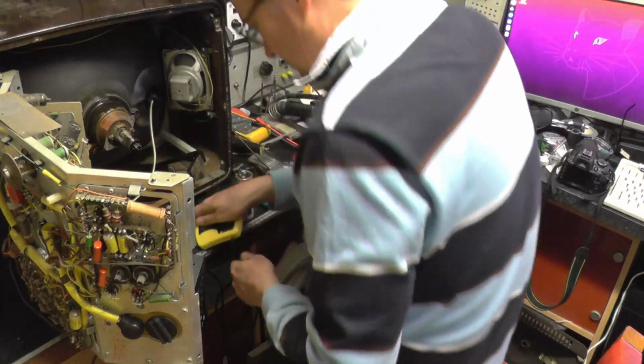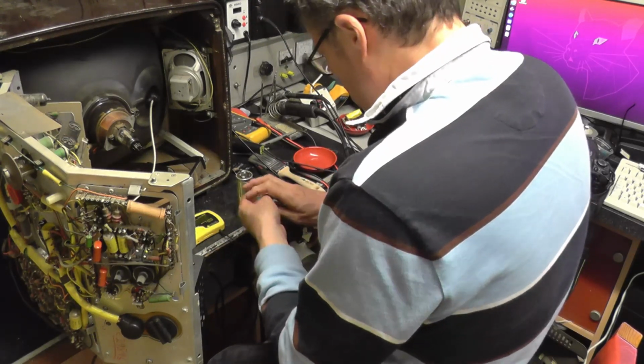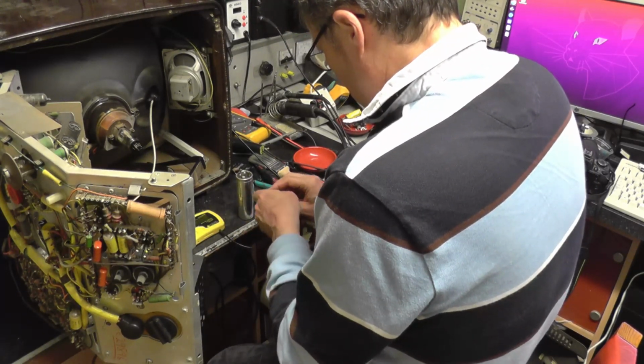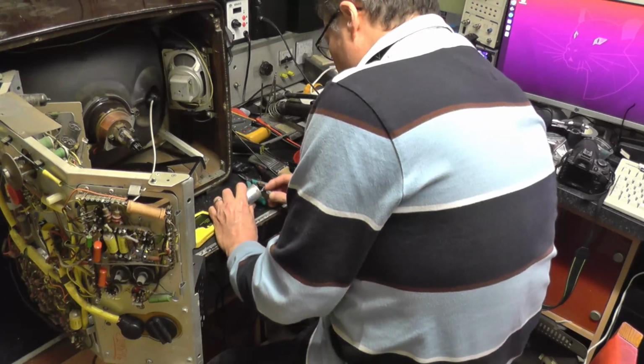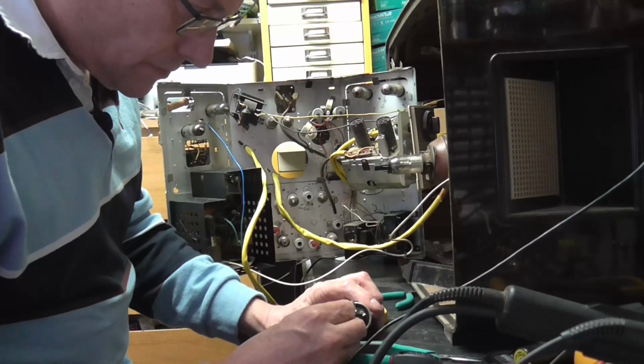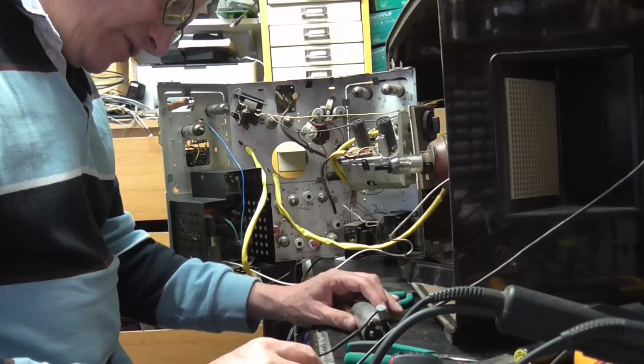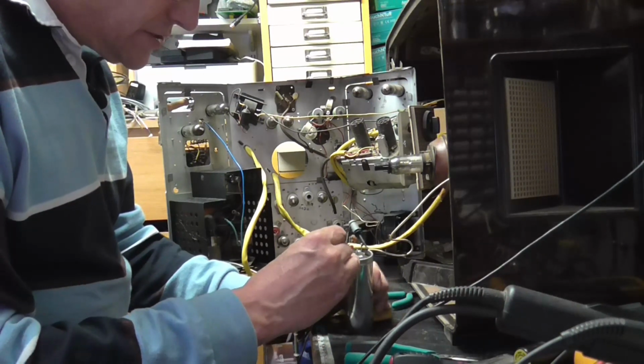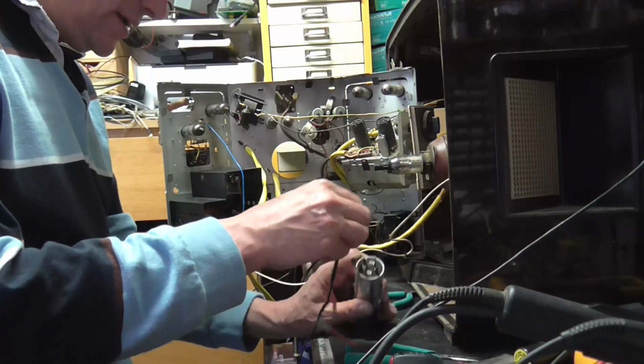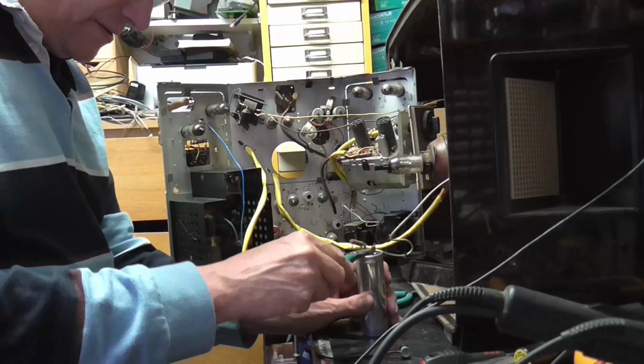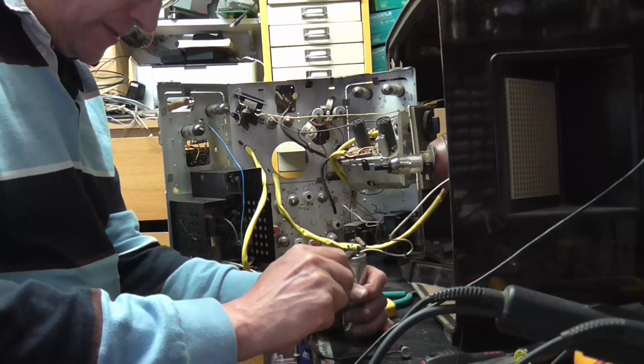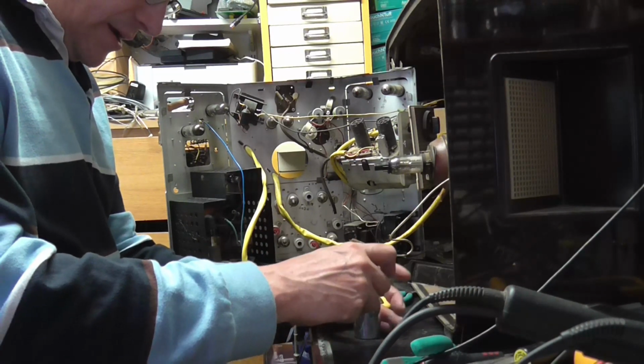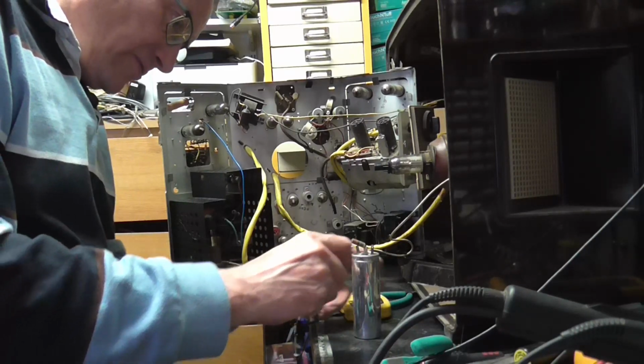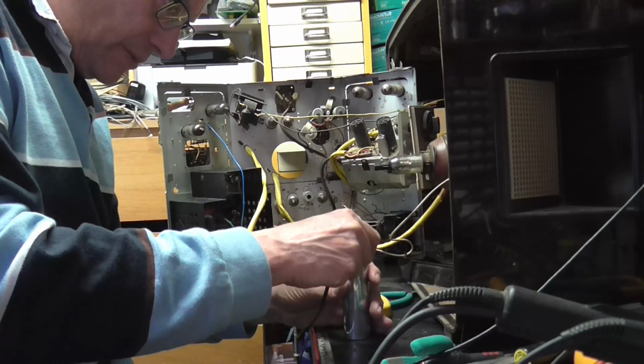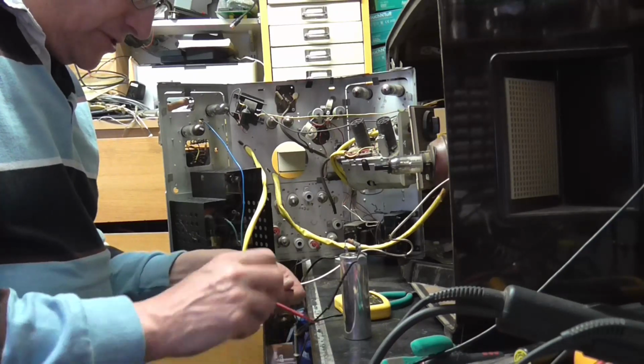Right, let's measure some capacitance for starters. So our common is there. Reading this back, what was our 250 volt? Yellow, 250 mic, sorry, yellow. I'll tell you one thing, let's just make sure - it hasn't been on for a day, but just make sure there's nothing stored in there, short it out. Otherwise it's a very expensive blowing up of the Peak component tester. So yellow is 250 mic.